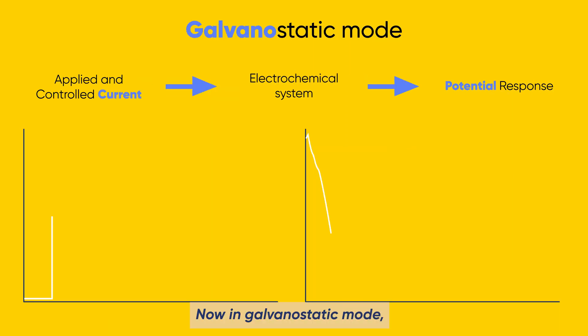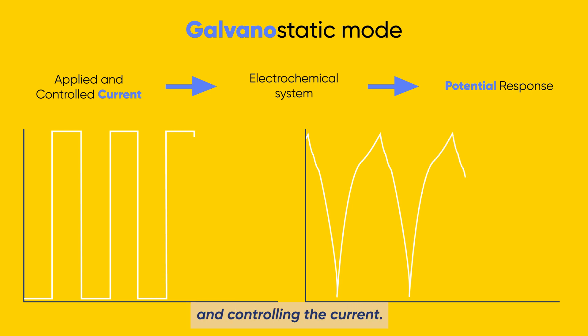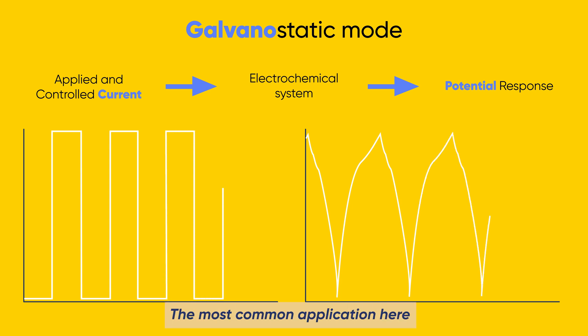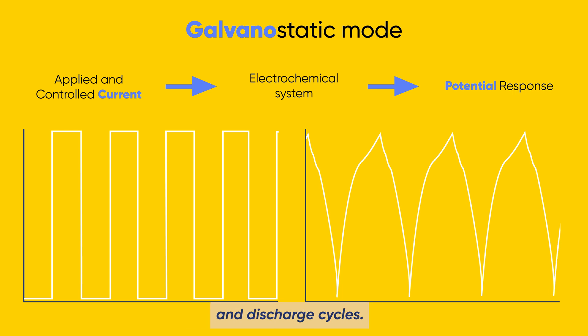In galvanostatic mode, the instrument measures potential variations while applying and controlling the current. The most common application here being battery and battery materials testing, such as repeated charge and discharge cycles.